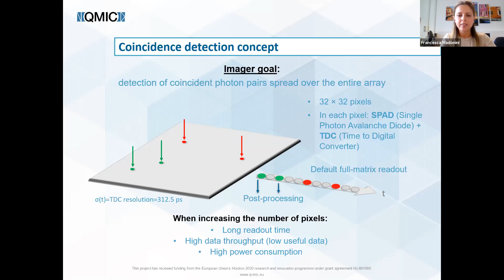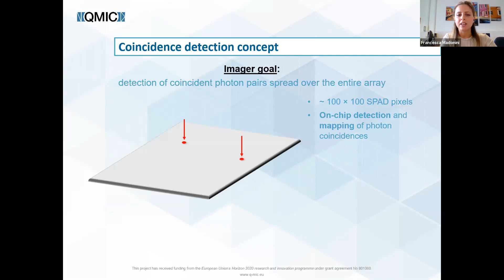That's why, with the aim of increasing the number of pixels, reaching almost 100 by 100 SPAD pixels, we developed a completely new array with a different detection concept, which is an on-chip detection and mapping of photon coincidences. To clarify this concept: if a single photon impinges, nothing happens. If another single photon impinges, nothing happens. But when a pair arrives within a coincidence time window of almost 2 nanoseconds, an event-driven logic is activated, transferring outside a strobe signal indicating the presence of a coincidence and the X and Y position of the coincident pairs. And again, if a single photon impinges, nothing happens.